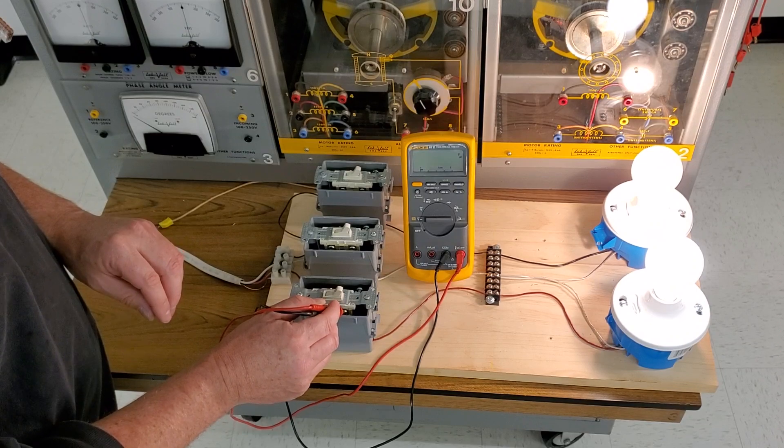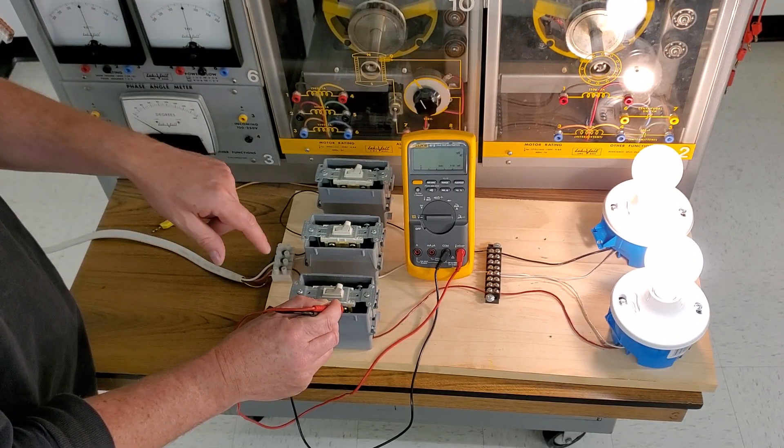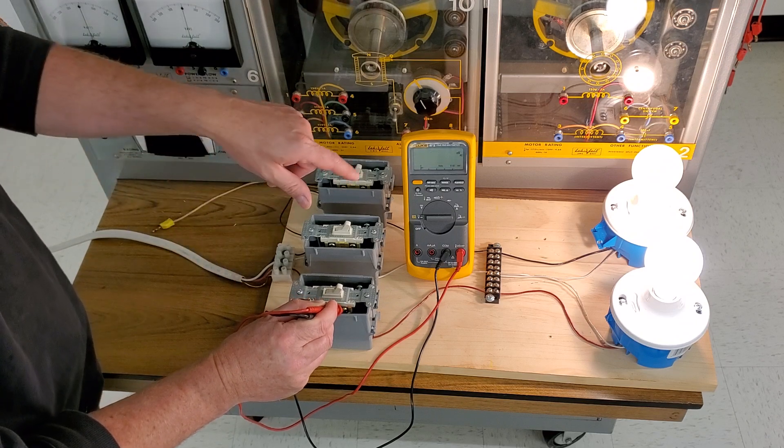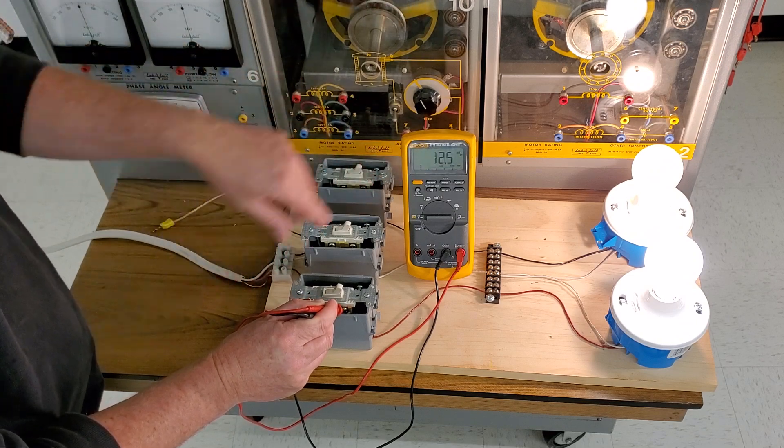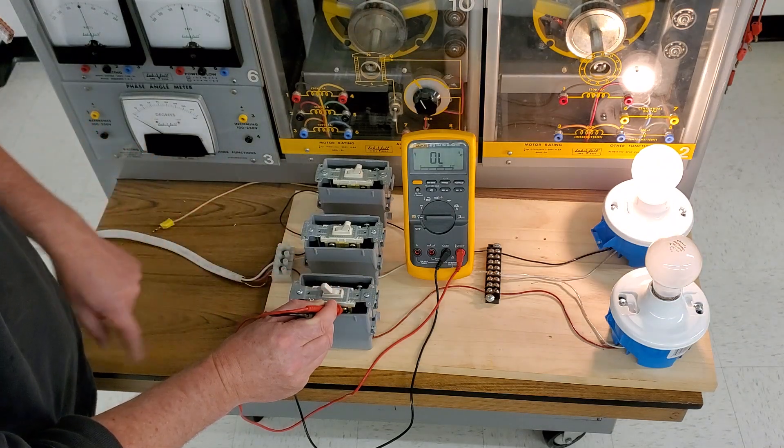Another quick troubleshooting technique: if we go across a switch and the switch is closed right now, we're reading in the millivolt range, which is basically zero volts, because we're reading across the same circuit.